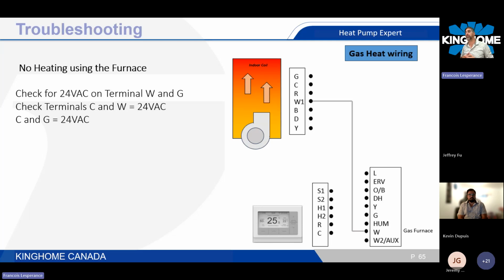If you don't have heating using the furnace, it's really important to check at the terminal on your furnace directly whether you have 24 volts between C and W1, for example. If you do, then this is not a thermostat issue, because your thermostat is calling.